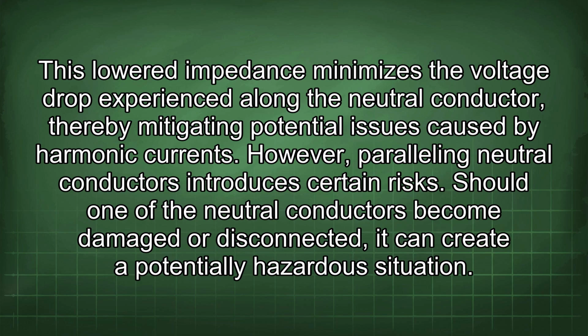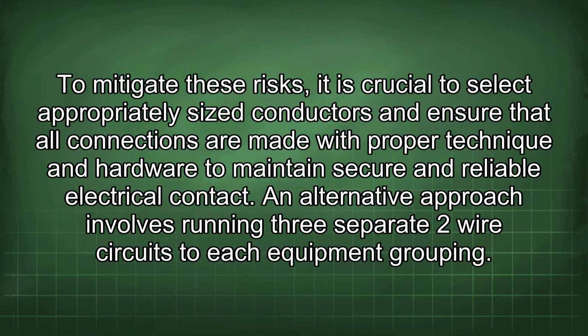However, paralleling neutral conductors introduces certain risks. Should one of the neutral conductors become damaged or disconnected, it can create a potentially hazardous situation. To mitigate these risks, it is crucial to select appropriately sized conductors and ensure that all connections are made with proper technique and hardware to maintain secure and reliable electrical contact.